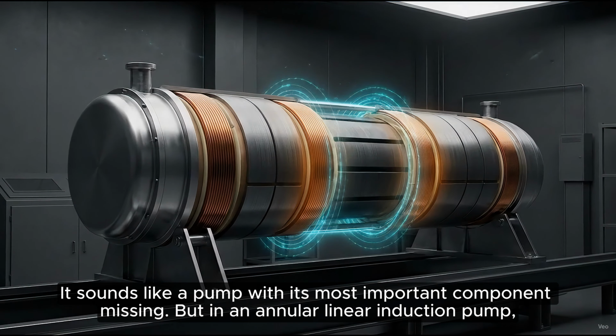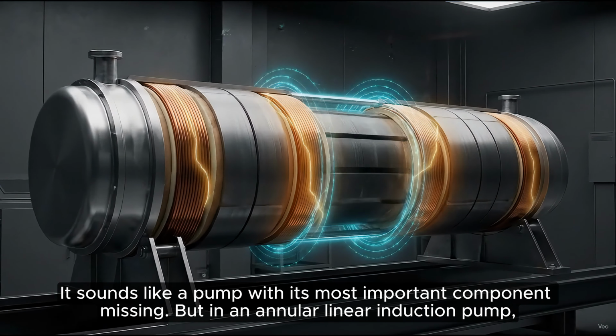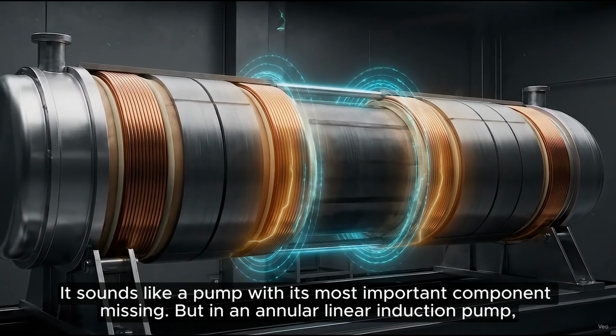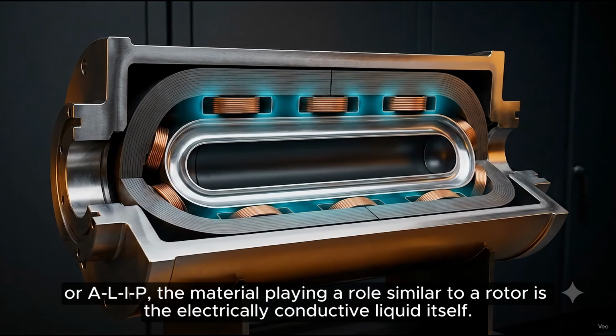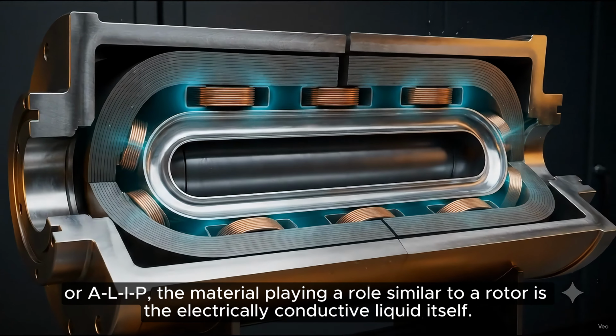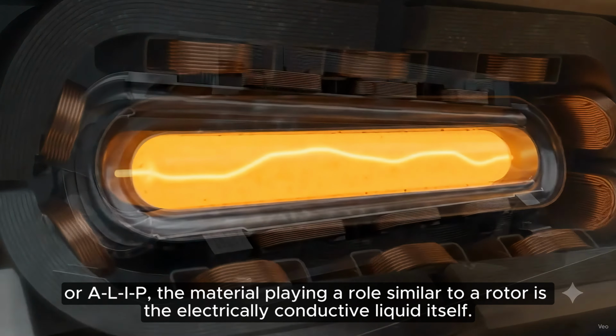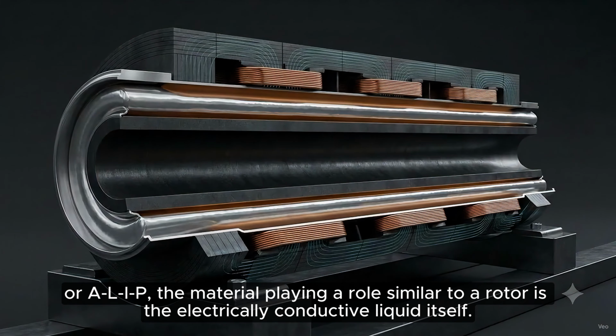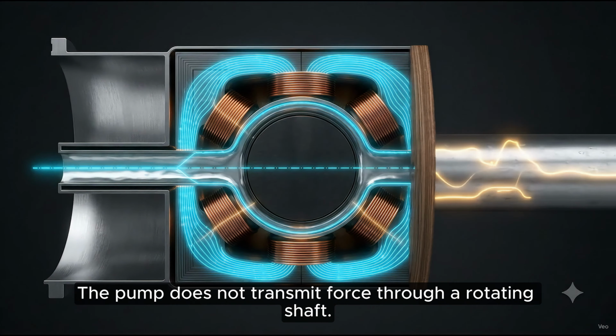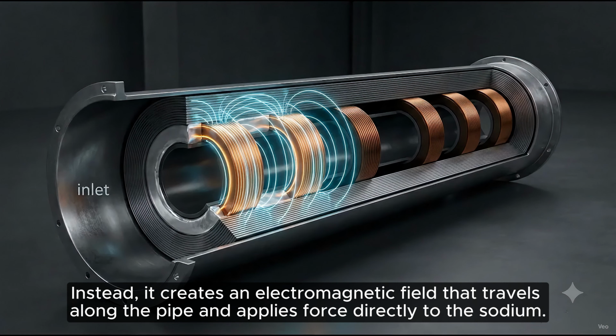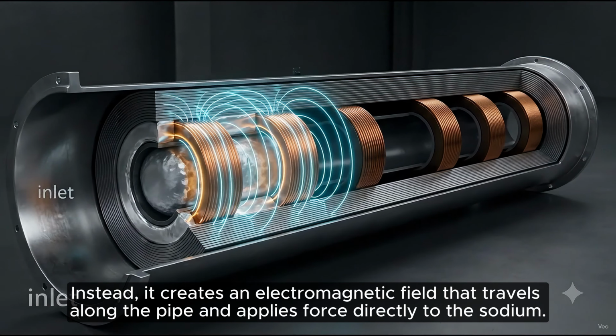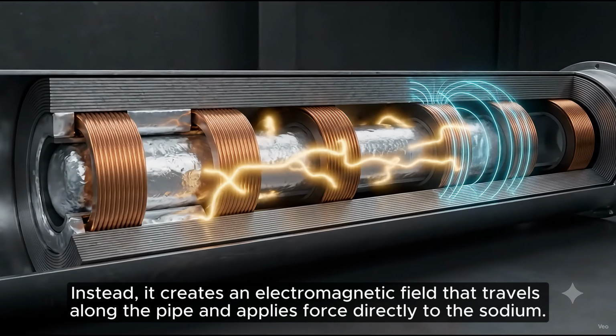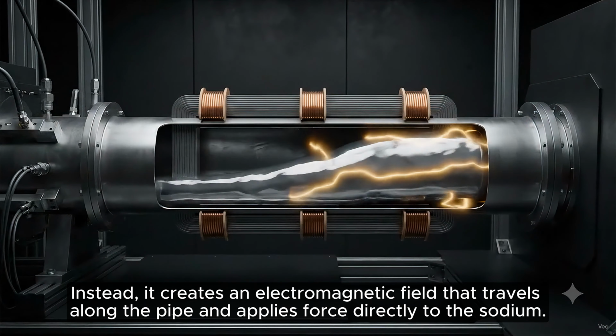It sounds like a pump with its most important component missing. But in an annular linear induction pump, or A-L-I-P, the material playing a role similar to a rotor is the electrically conductive liquid itself. The pump does not transmit force through a rotating shaft. Instead, it creates an electromagnetic field that travels along the pipe and applies force directly to the sodium.